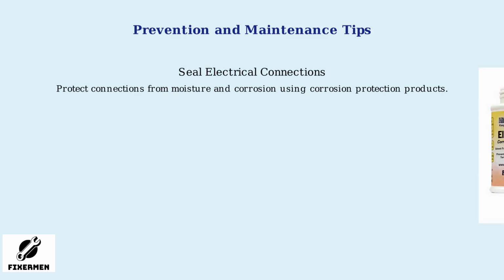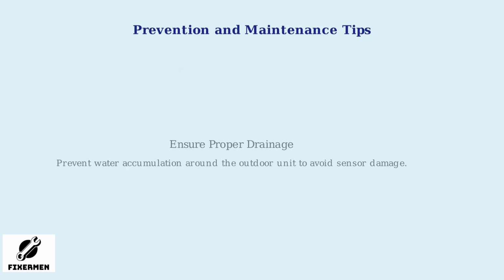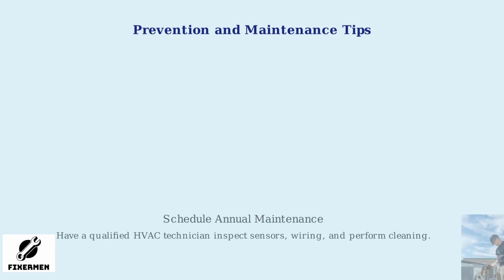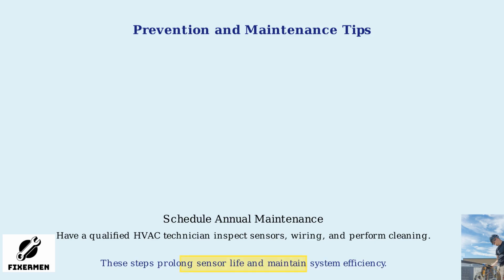To prevent future occurrences of error code 223, implement proactive maintenance measures. Seal all electrical connections to protect them from moisture and corrosion. Ensure proper drainage around the outdoor unit to prevent water accumulation, which can damage the sensor. Schedule annual maintenance checks with a qualified HVAC technician to inspect the sensor and wiring and to perform any necessary cleaning or adjustments. These steps will help prolong the life of your sensor and maintain the efficiency of your Lennox system.